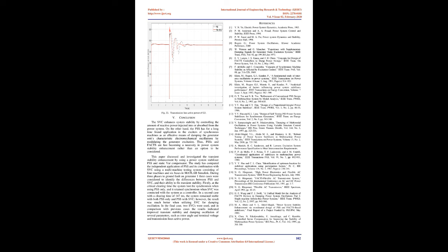SVC settled faster, with settling times of 11 s and 10.3 s, than with only PSS, 13 s and 13.3 s, and the peak amplitude of both rotor angles with SVC was reduced to 79 and 67 degrees, respectively. With only PSS, the corresponding values are 87 and 70 degrees.